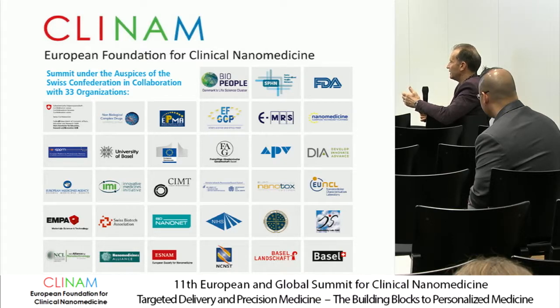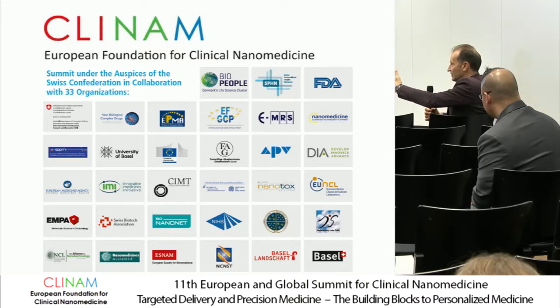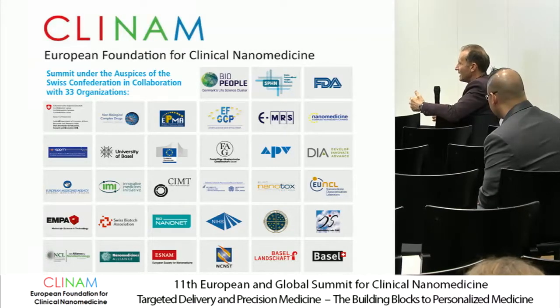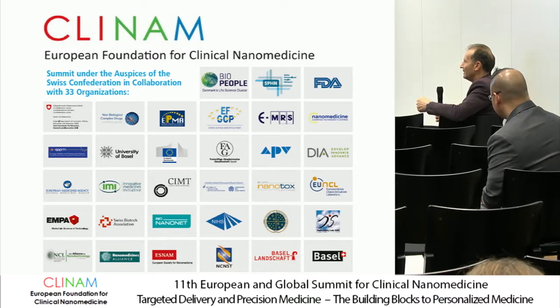So there are ISO standards for DLS, and you push the same button 25 times. The data's still subject to huge errors, because of a tiny little change in the refractive index or the temperature or the viscosity, and you can't control those variables. So it's inherently the wrong technique. And it doesn't matter how much you standardise it, you'll never ever get to the right technique for that.